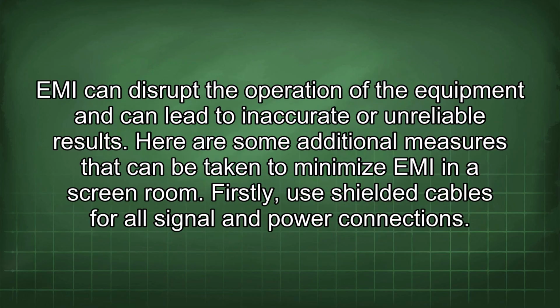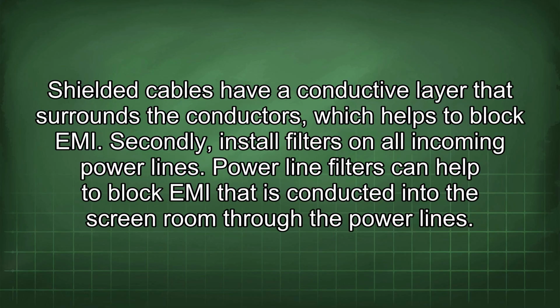EMI can disrupt the operation of the equipment and can lead to inaccurate or unreliable results. Here are some additional measures that can be taken to minimize EMI in a screen room. Firstly, use shielded cables for all signal and power connections. Shielded cables have a conductive layer that surrounds the conductors, which helps to block EMI. Secondly, install filters on all incoming power lines. Power line filters can help to block EMI that is conducted into the screen room through the power lines.